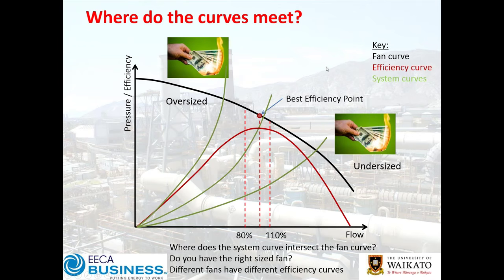What does this translate to in terms of where the fan curve and system curve meet? With a good design incorporating the system curve correctly, we can design our system to run close to the best efficiency point — say 85% efficiency. Undersizing or oversizing the fan can result in operating quite a ways from that efficiency point. With an undersized fan, you're going to struggle to get the pressure you need.